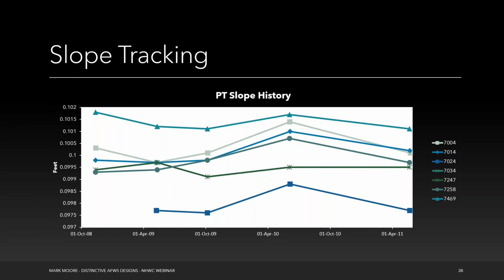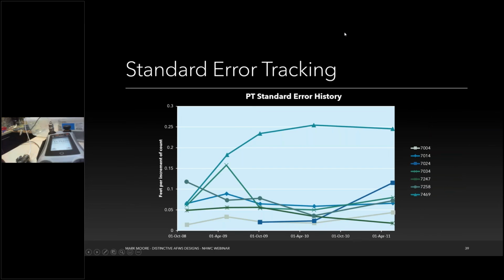But when you're tracking that, also track what calibrator was used. Because if you find out 6 months later that one of your calibrators was in need of calibration itself, you want to know what sites were visited and go and correct that. And then you can also track things like standard error. Do things suddenly change, or is it a gradual change? You can track the offset.